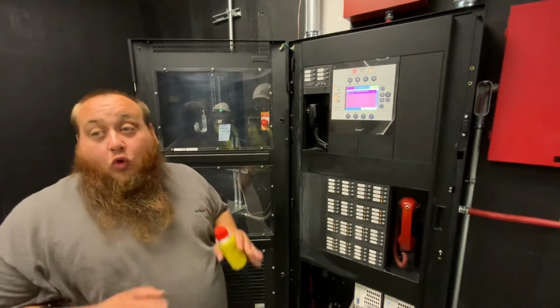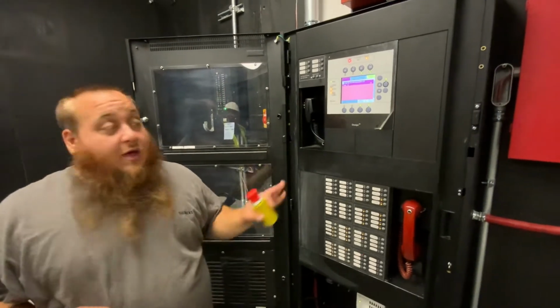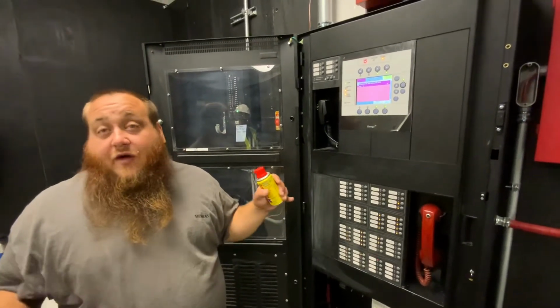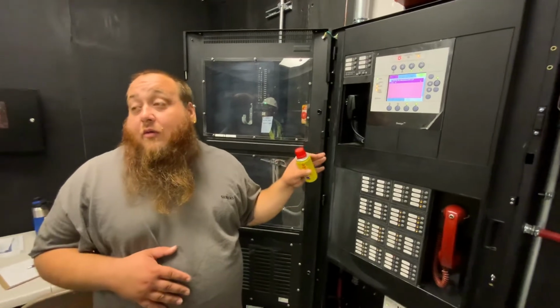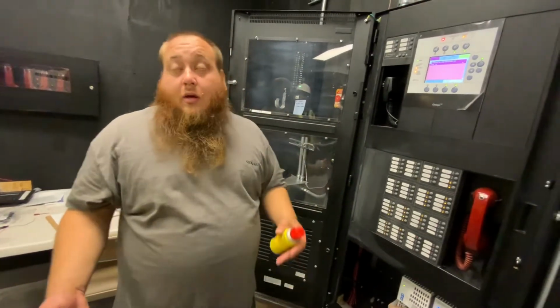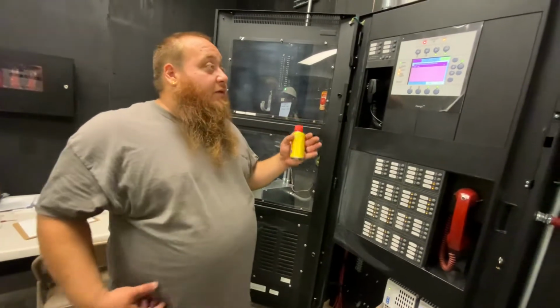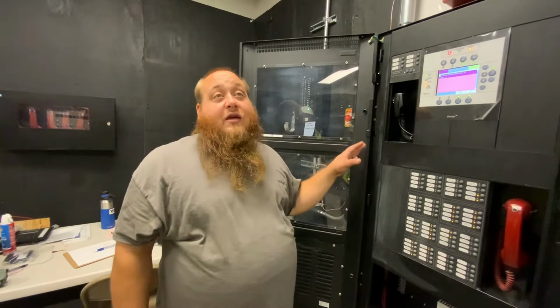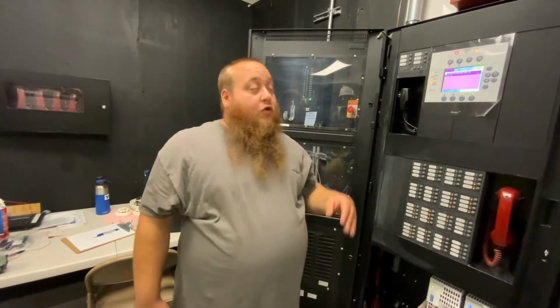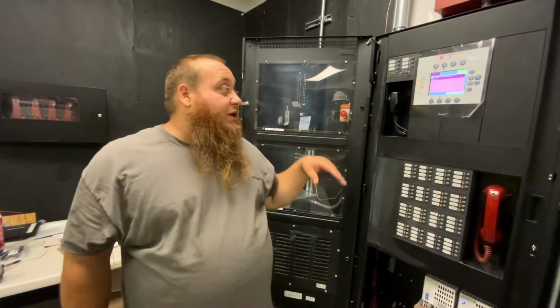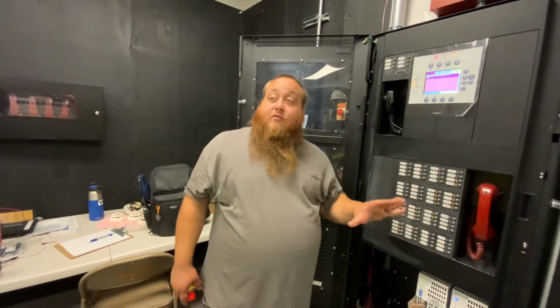If it's a normal live situation, you're not allowed to reset that panel because the fire marshal and others are going to want to see what's going on. If you're working on the building, systems taken out, things on test and bypassed, and they know they're working on it, then you can reset it. Otherwise, once they get that dispatch, they're going to want to come check things out, and if you reset it, they might get upset with you. So if it's a real situation, you can silence it but do not reset.